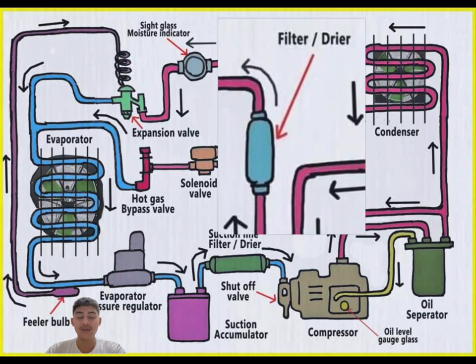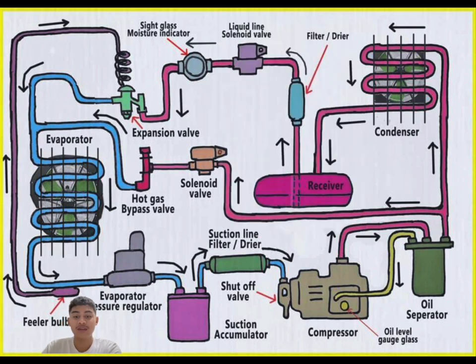And then we have the filter slash dryer. The function of this filter is to remove moisture and debris from the refrigerant. Why is it important? Moisture can freeze and block the expansion valve. Debris can damage the components.